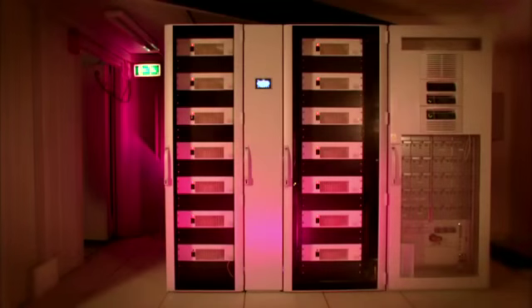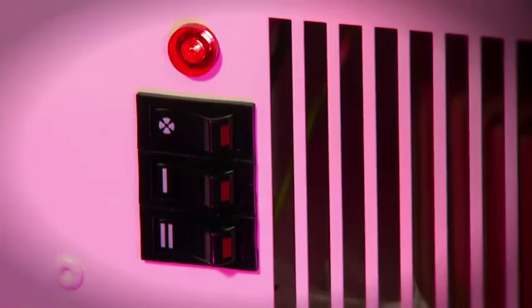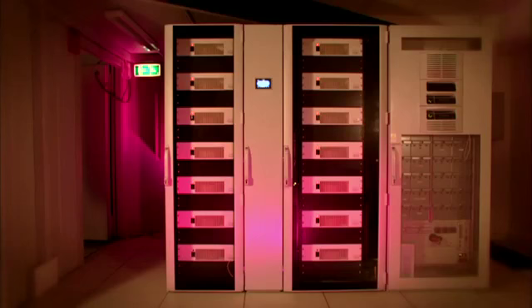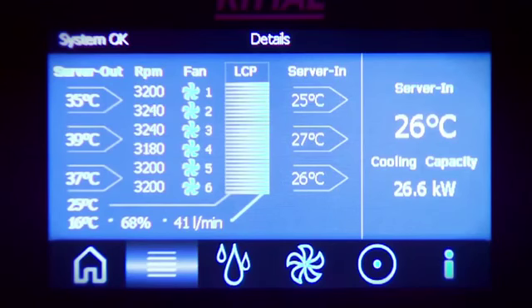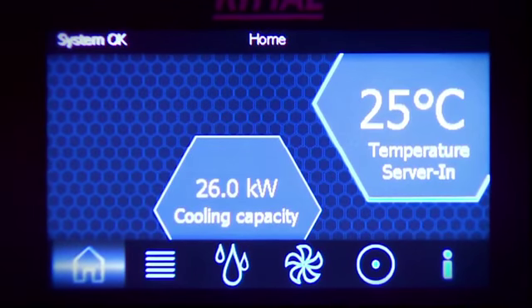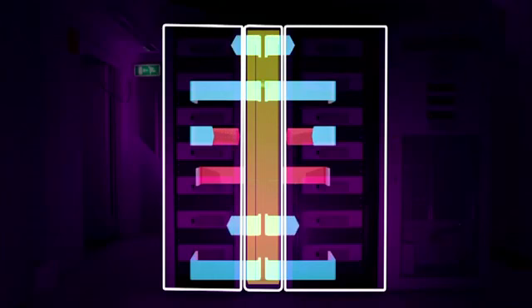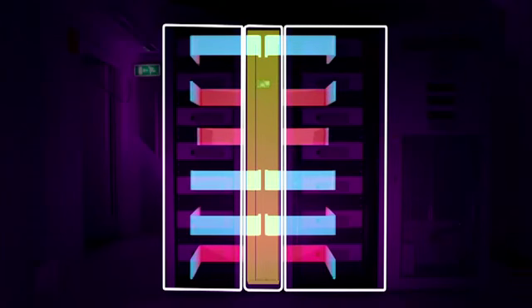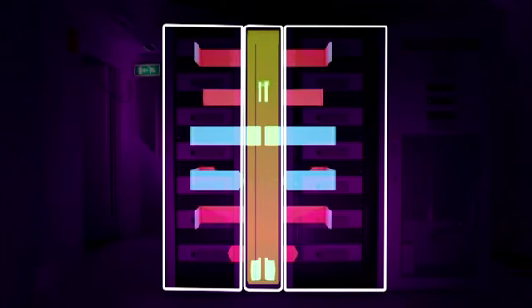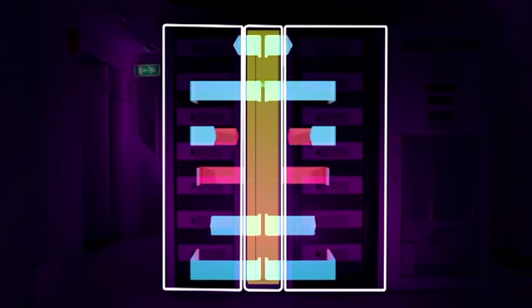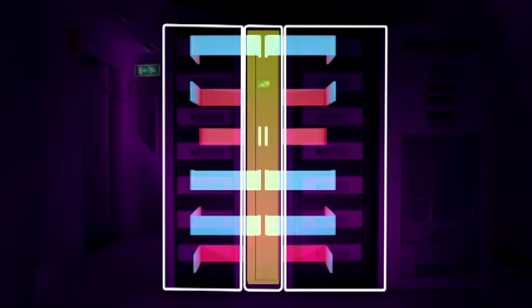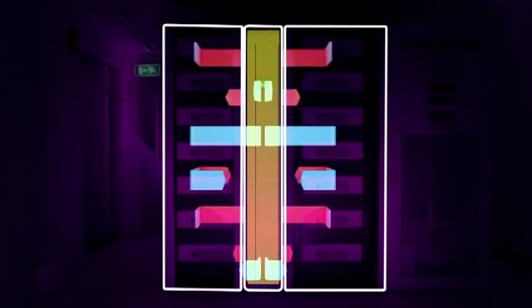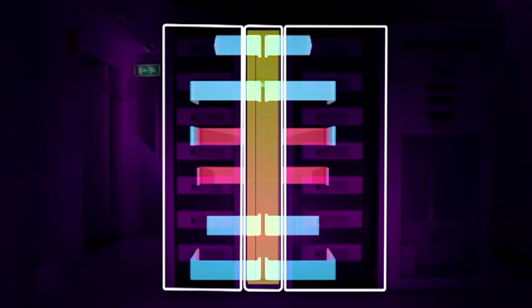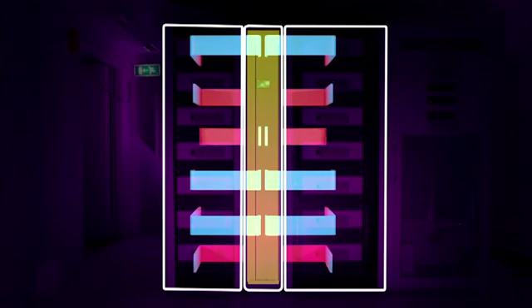As can be seen in this demonstration, heat loads have been placed in the enclosure to mimic high-power blade servers. The heat load has been taken up to 20 kilowatts, and you can see the inlet and the outlet temperatures are stable. Because of the large cooling capacity of the LCP Plus, it can be shared across a number of enclosures, effectively providing 2 enclosures with up to 15 kilowatts per rack. This gives you a greater flexibility to use the LCP Plus wherever and whenever you need to.